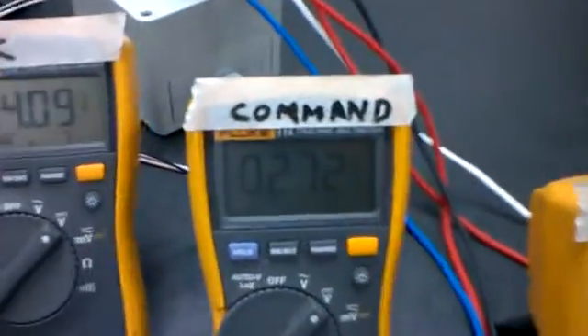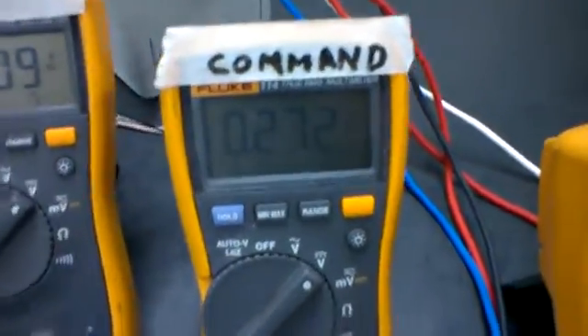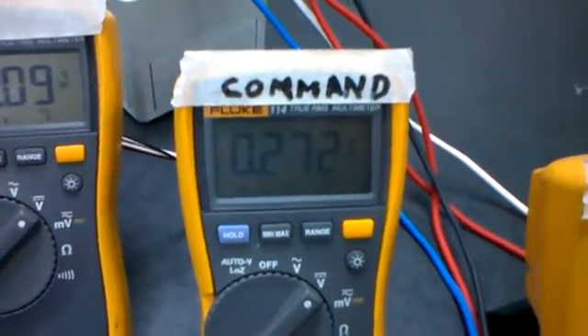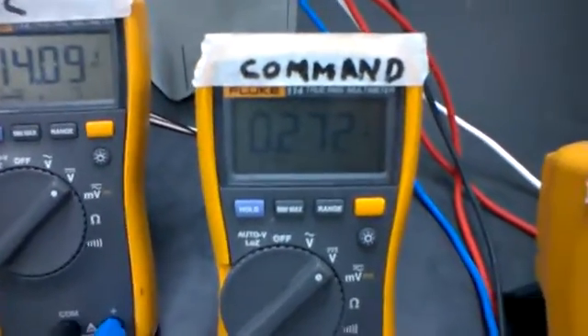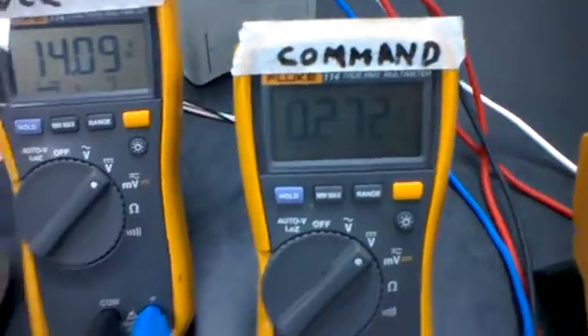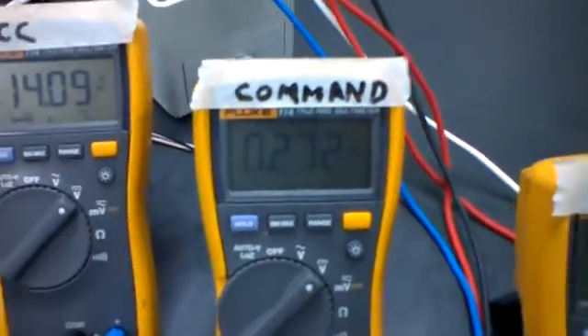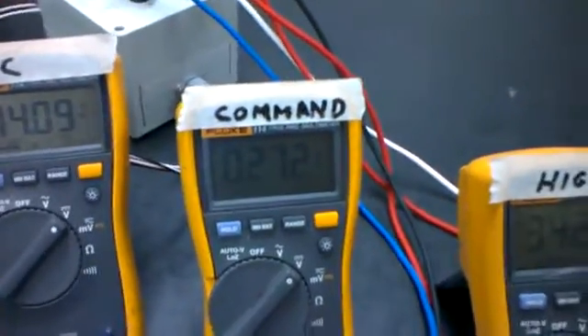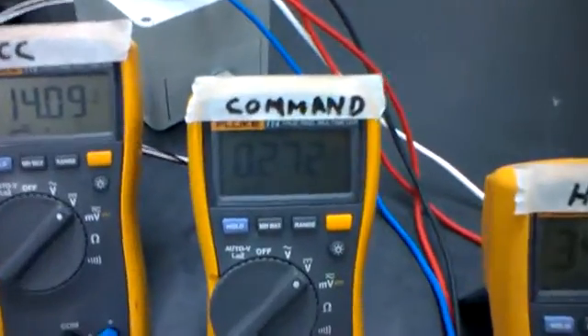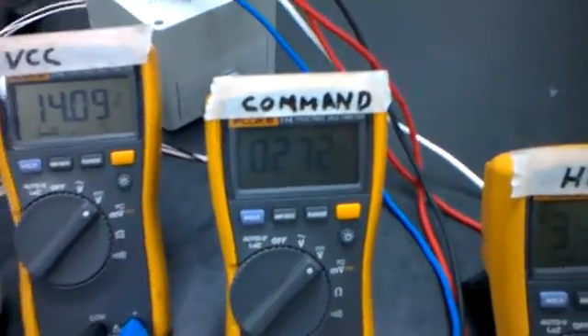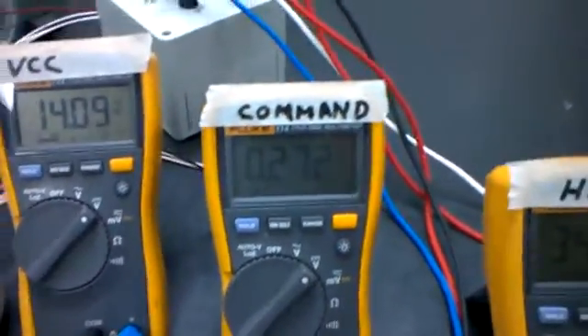The second one is a command voltage, and this is actually what sets the motor speed. It will increase to give it a speed increase. So it works somewhere anywhere between 1 and 5 or 1 and 6 volts DC, and the voltage will increase to provide a signal to the motor to increase speed, and then it will decrease to allow it to decrease speed.